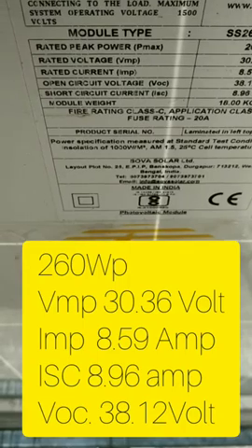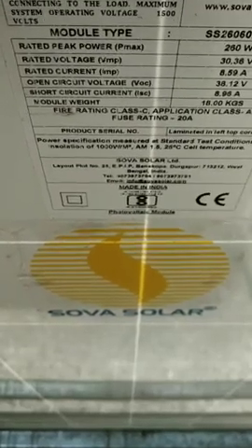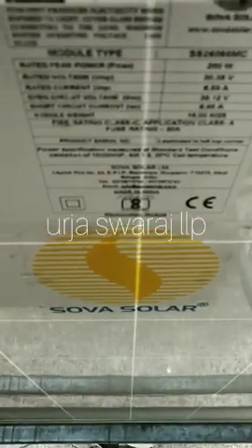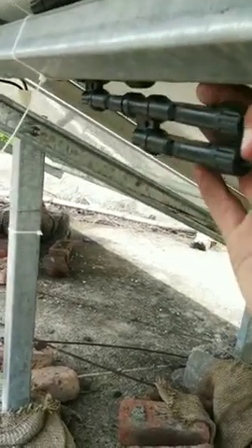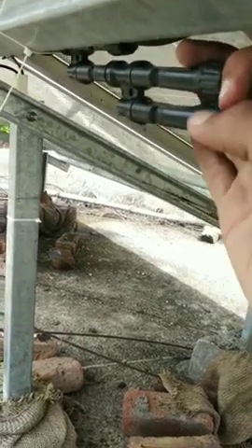All the above specifications are on the STC condition, standard test condition. So it is nothing but radiation irradiance is 1000 watt per meter square, air mass is 1.5, and cell temperature is 25 degrees Celsius. Okay, now all modules are connected in parallel combination because of the design. We will discuss design in the next theory session. So you will understand why all modules are connected in parallel.